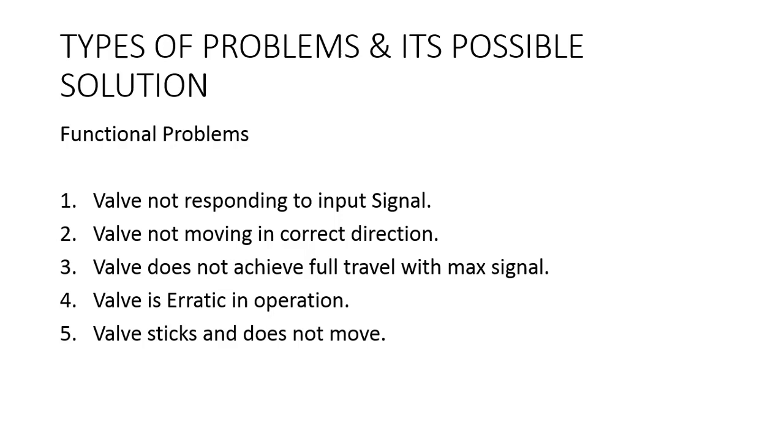Valve stuck, so there we need to check where the problem is. Is it in the valve, or in the actuator, or between the coupling of the actuator stem and the valve stem? Second, valve not moving in correct direction.